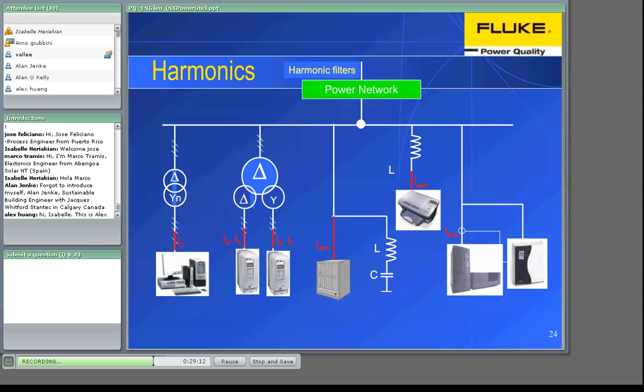This slide shows some situations that can be faced in a network. From the left side, we have a delta-wye transformer, which is typical at medium and low voltage levels and can trap triple harmonics. Now, assuming that there is a generation of the third harmonic at the low voltage level, as mentioned, triple harmonics enter the neutral, returning to the start point of the transformer. They will be stopped at the primary. The advantage is they are stopped. The disadvantage is the primary will warm up and saturate.